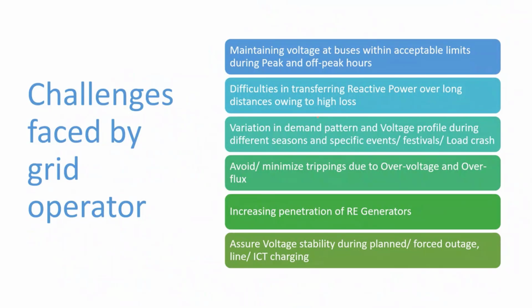So coming back to the point, voltage is a very important quantity at the substation level. It impacts your overall power transfer. You create a high voltage system so that you can send a large amount of active power from one place to another, because at a lower voltage the amount of current will be very high for the transfer of the same amount of power, which is not justifiable or technically possible.